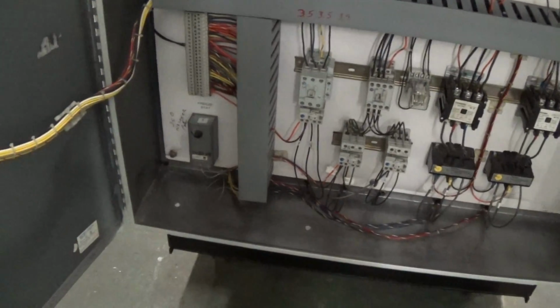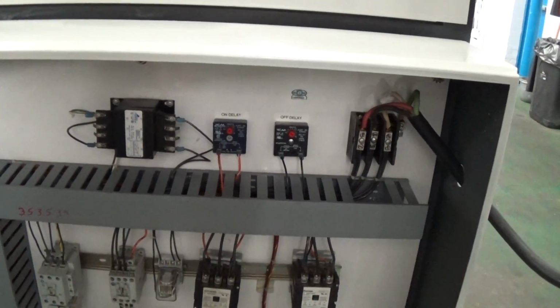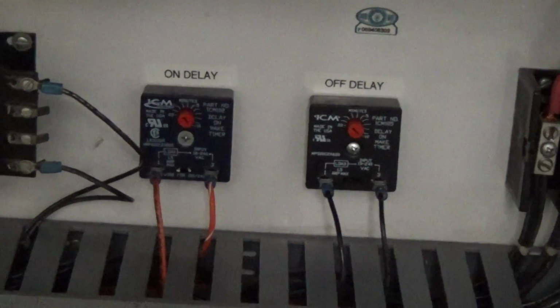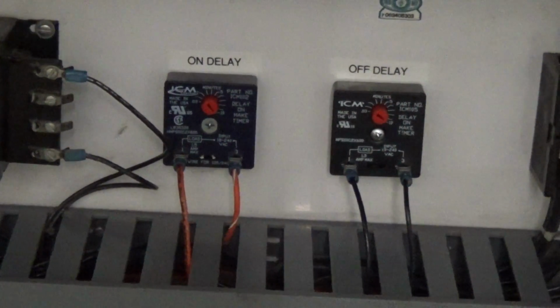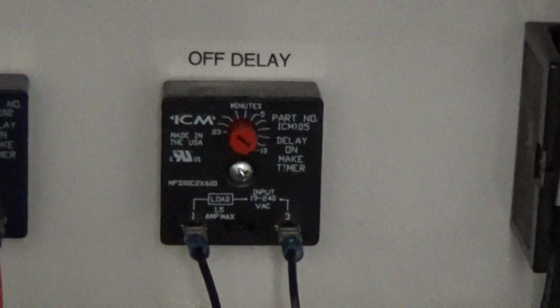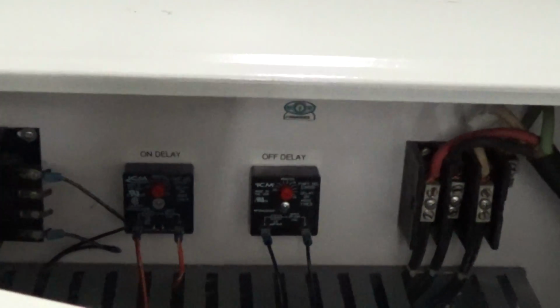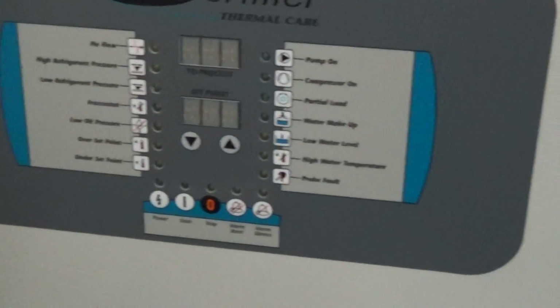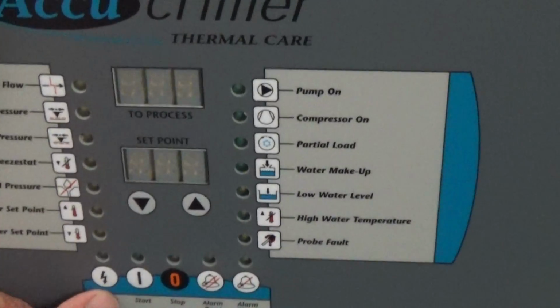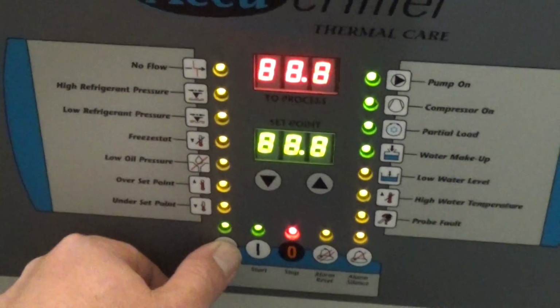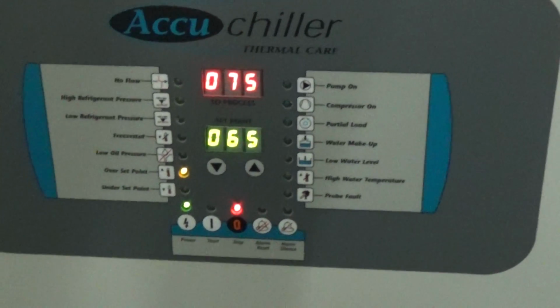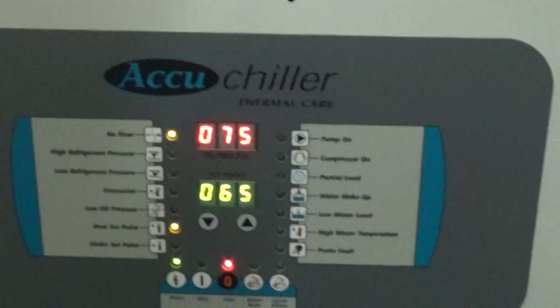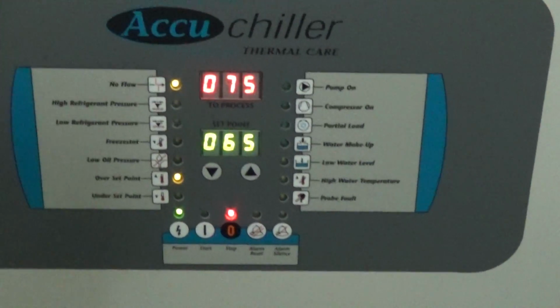What we have inside here, we did paint the inside of the control cabinet a little bit more, and we actually went ahead and added 2 timers here, one for compressor on delay, that's hooked up to one compressor, one for compressor off. The compressor off is tied in with the hot gas bypass circuit. We added those ourselves in addition to this relay, and those two things combined give you some level of control. Oh, I'm sorry, I was pressing start, not power. That gives you some level of control over the staging of the compressors. Because in standard form, the unit would turn both compressors on at once. We just want to give the customer a little bit more flexibility than that.